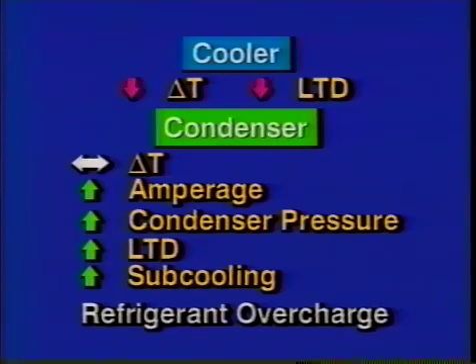To resolve the problem, some refrigerant needs to be recovered from the chiller to bring the charge back to within design parameters. When recovering the refrigerant, use EPA-approved environmentally sound procedures.